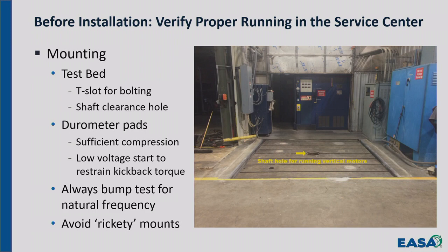Okay, so you can do a bump test on it right here. It's such a simple thing to do. It probably takes 15 minutes to do a bump test, and you can document that. And if a question ever comes up about it, you've got that in your documentation, and you can check it with the manufacturer, see if it matches what the manufacturer says it should be, and understand that it has nothing to do with what you're encountering on site, because what you're encountering on site is an installed reed frequency of the motor on a pump. Okay?